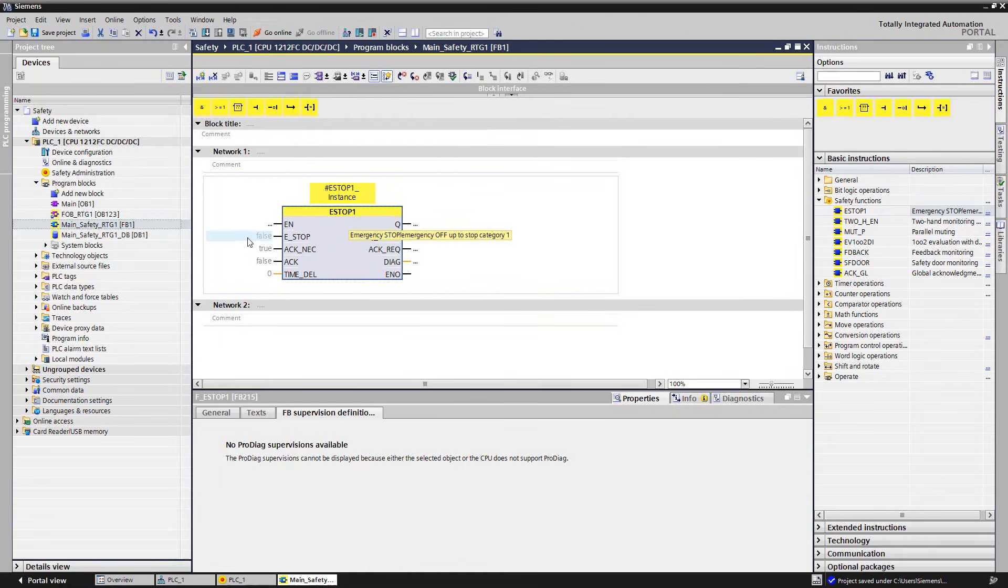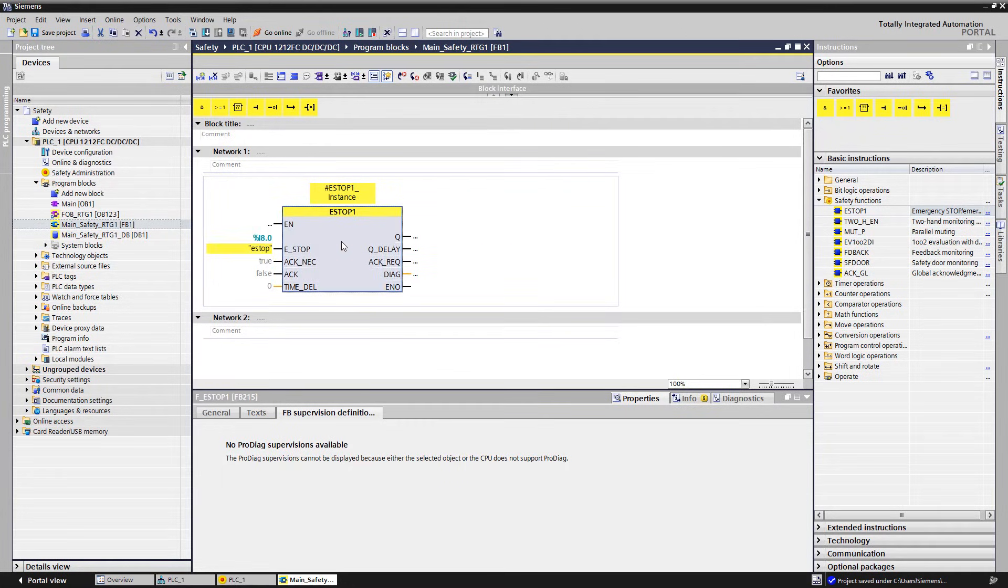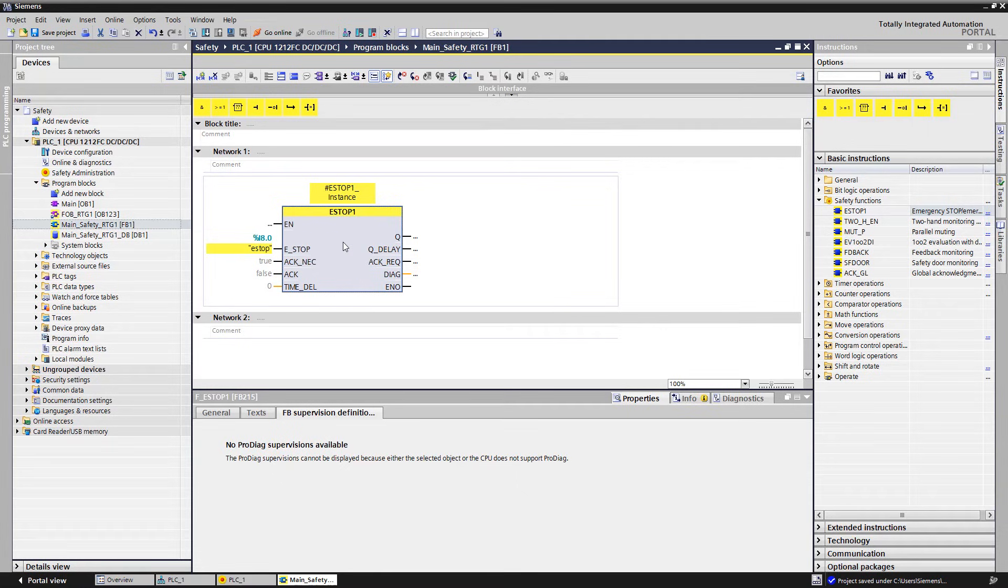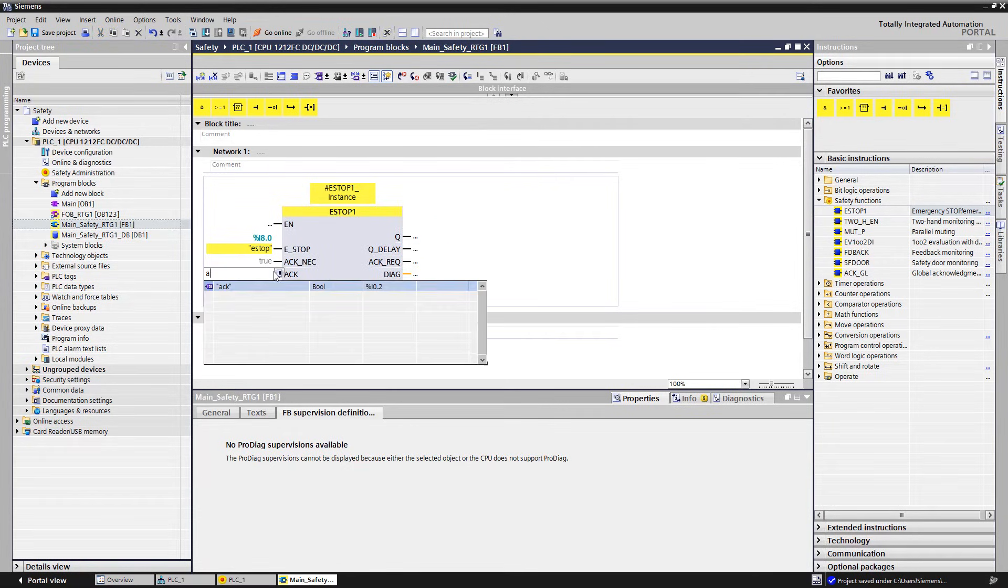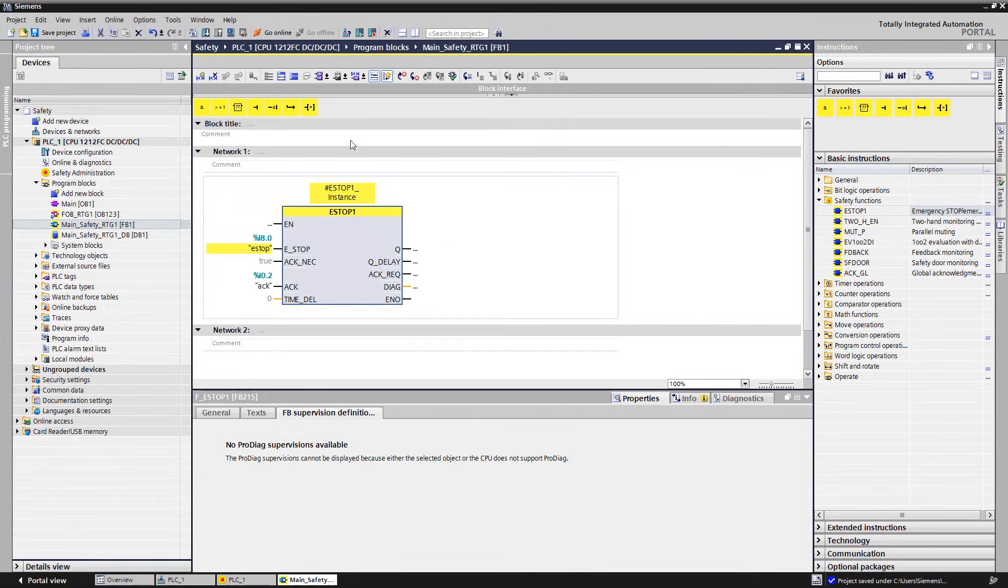The input parameter e-stop is connected with our variable e-stop. In this context, ACK NEC means that an acknowledgement is always required when the emergency stop is actuated. This acknowledgement is initiated via input ACK.